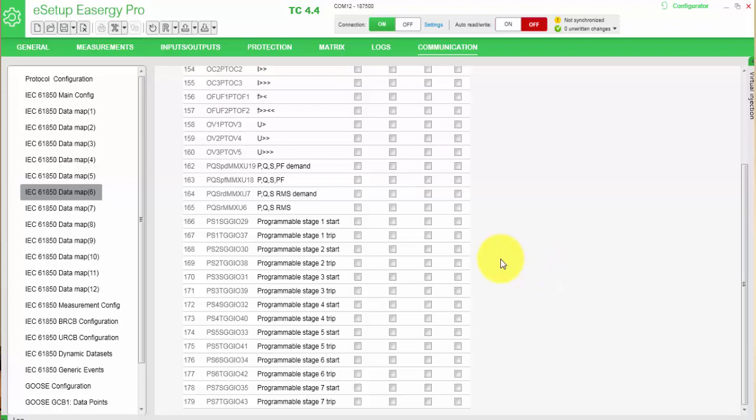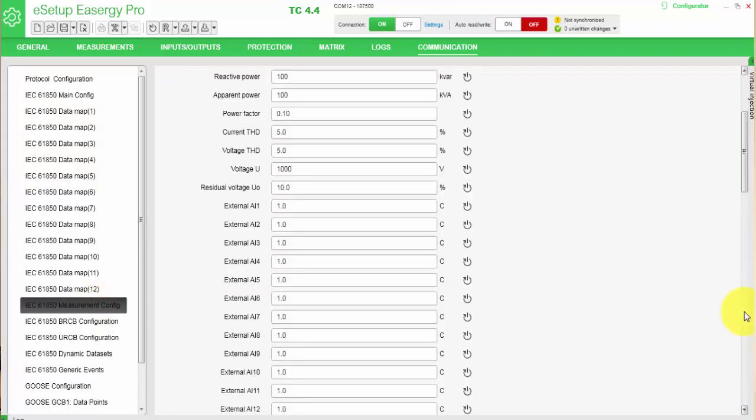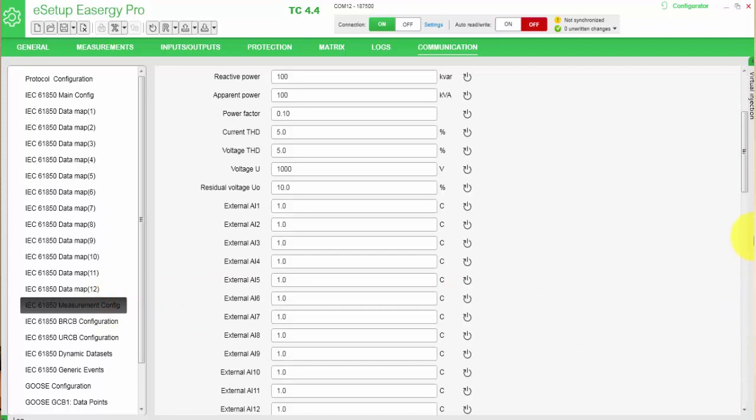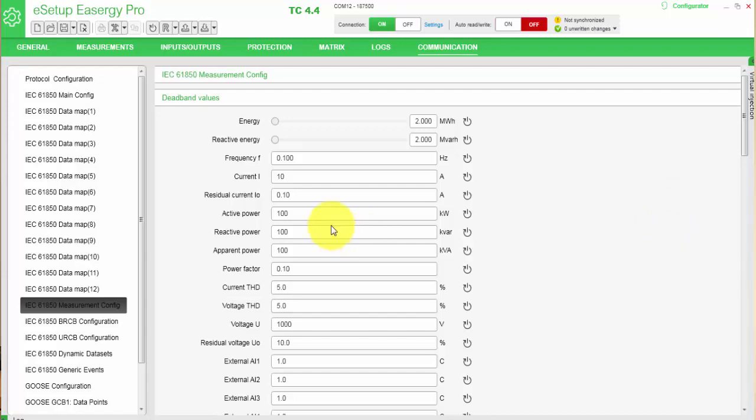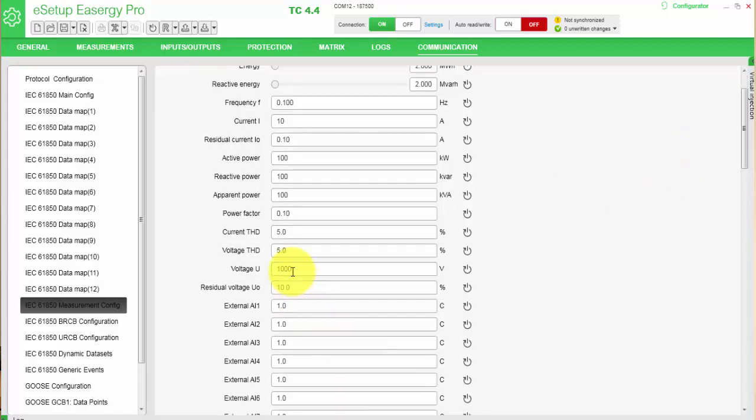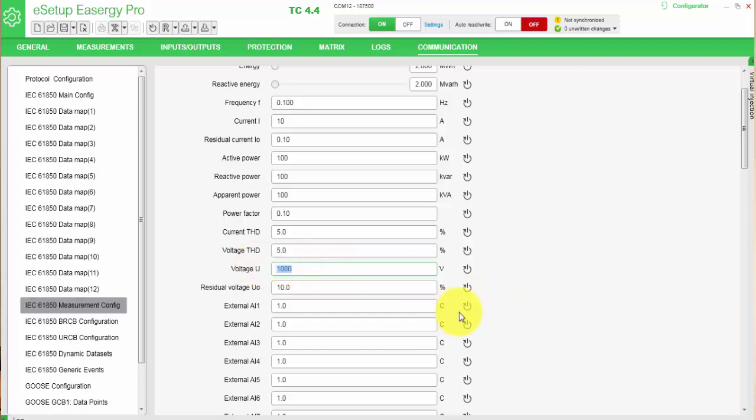So the next step would be that we go to the measurement configuration. In measurement configuration, we can define threshold of the current, which means the level has to change a certain amount before we create an event and update the dataset. In this case, we have a current threshold of 10A. We can leave it like that, and we have a voltage of 1000V. So we could lower that, we'll put it to 10V as well.